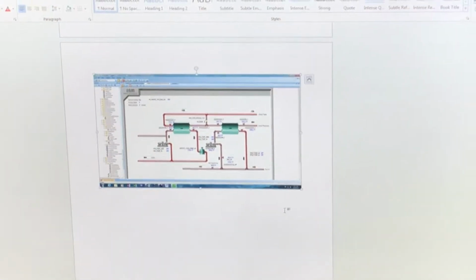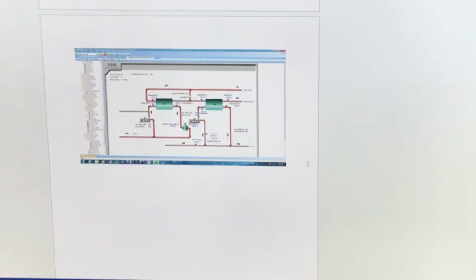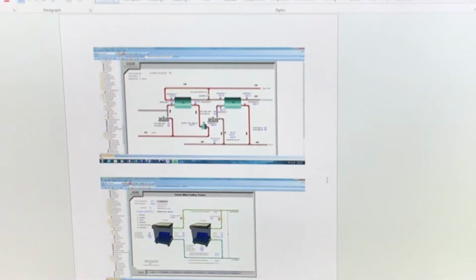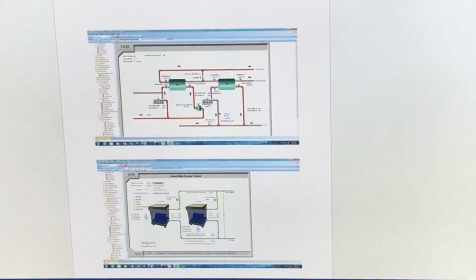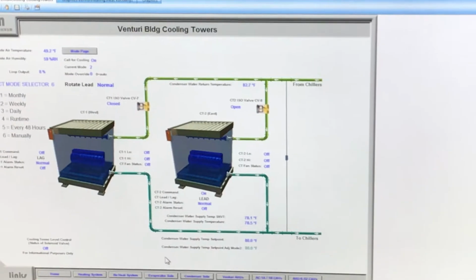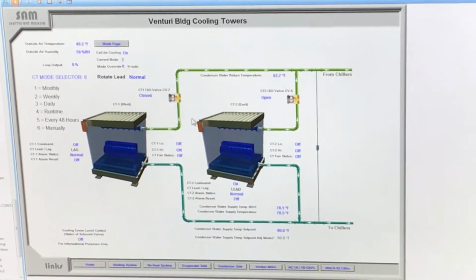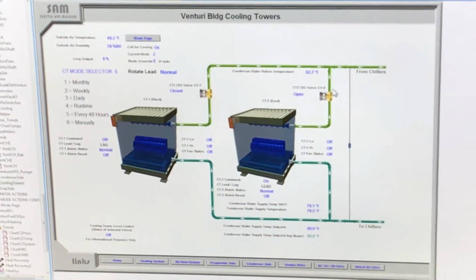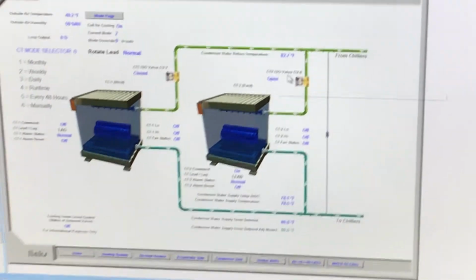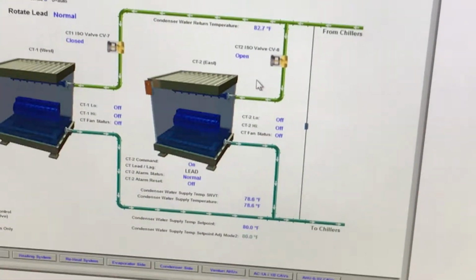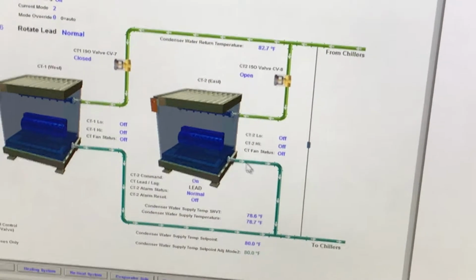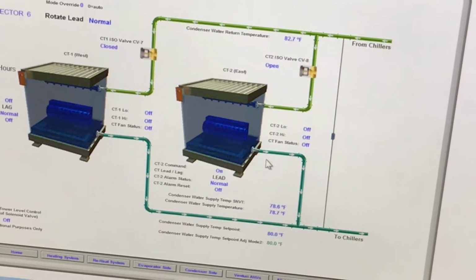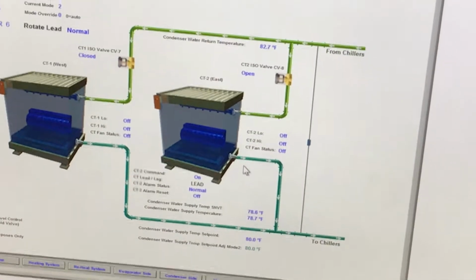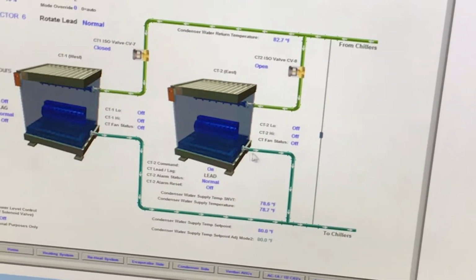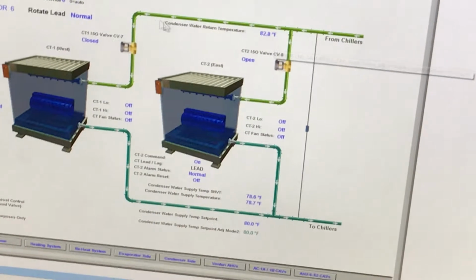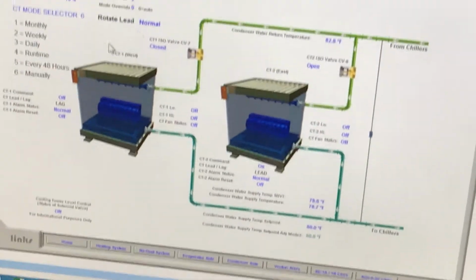And something else: whatever cooling tower is the lead cooling tower at that time, the valve above that brings the water in and through the media will always be open, even at 0% loop output. It will always be open to the lead tower. So we can always have some flow. That is correct. We haven't had too many problems with the cooling towers. That's good. So I think that's it.